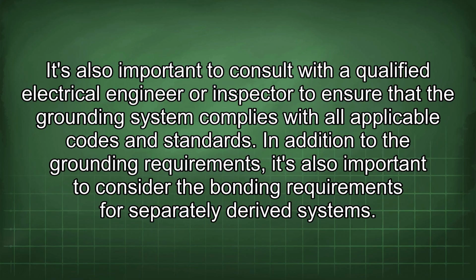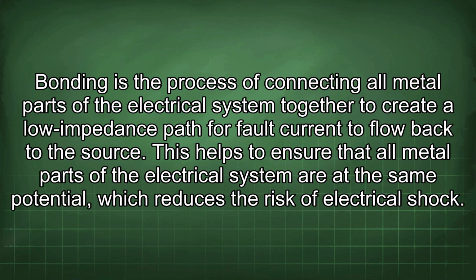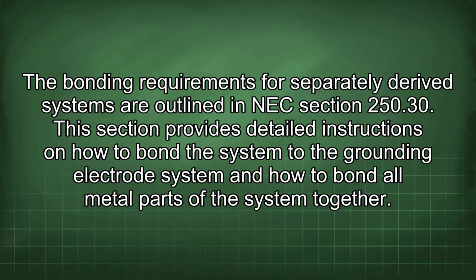In addition to the grounding requirements, it's also important to consider the bonding requirements for separately derived systems. Bonding is the process of connecting all metal parts of the electrical system together to create a low impedance path for fault current to flow back to the source. This helps to ensure that all metal parts of the electrical system are at the same potential, which reduces the risk of electrical shock. The bonding requirements for separately derived systems are outlined in NEC section 250.30. This section provides detailed instructions on how to bond the system to the grounding electrode system and how to bond all metal parts of the system together.